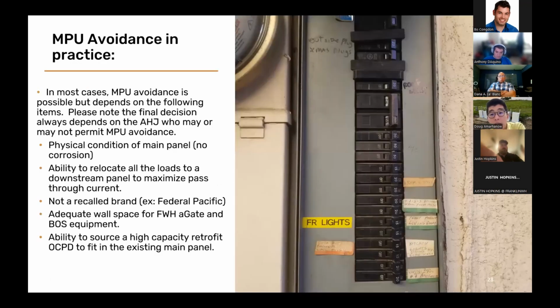This is the example I was looking for — probably a classic panel that was common in SoCal with 100 amp service. The things you need to look out for: we can't guarantee main panel upgrade avoidance, because it really comes down to the AHJ and the permitting at the end of the day. They typically look for whether the main panel is rusty and decrepit — if so, that's probably going to require a main panel upgrade. If it's in good condition, you're probably okay. Also check if you have space on the wall to relocate the loads within a reasonable distance, typically within 2 feet of the main panel. And the red-listed brands, like Zinsco or Federal Pacific, are definitely no-nos, along with your ability to source that specialized breaker we saw in the photo previously.